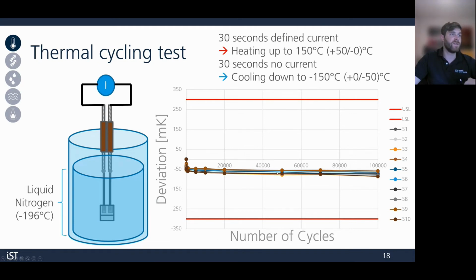So here we have 20,000, 50,000, 70,000, and we even take it a step further to 100,000 cycles. And again, we see there's very little drift. We have here the deviation in millikelvin, and this is from the two-bath test, and this is deviation in millikelvin of the resistance at 0. So we're extrapolating down to 0, and we see very little drift. The USL and LSL lines here are the allowable limits according to the detail spec.